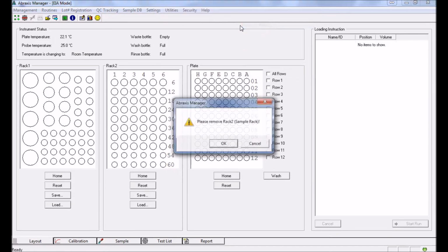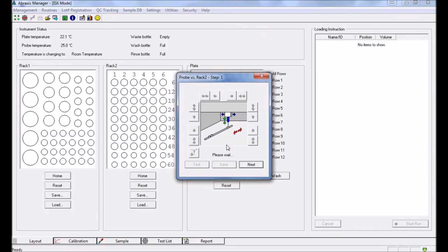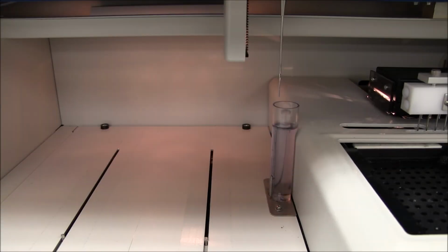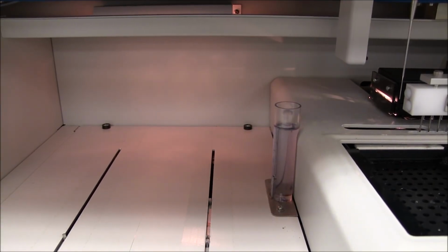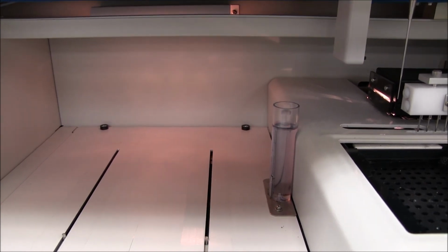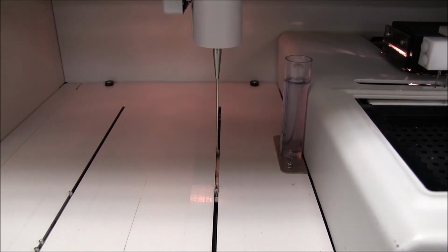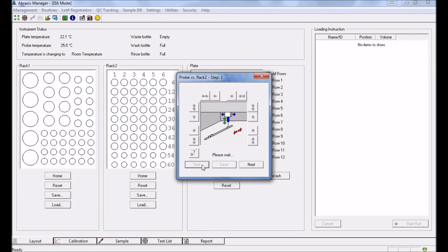At the top middle of the screen, click on Utilities, then Alignment, then choose Probe versus Rack 2. Click the Test button to see how the probe is currently aligned over the pin. In this situation, the probe could be moved very slightly to the right by clicking the single blue arrow once, then clicking the Test button to confirm. When satisfied with the adjustments, click Save, then Next. Select No for setting the alternative sample cup depth, then OK.